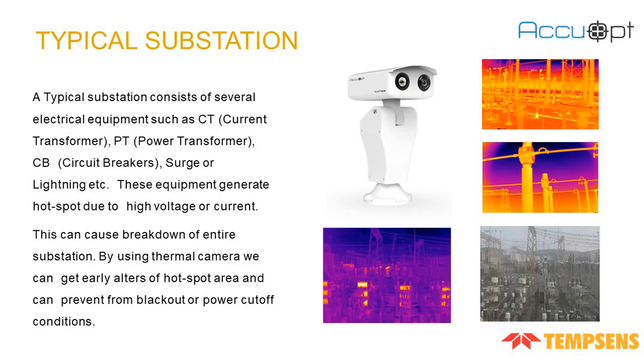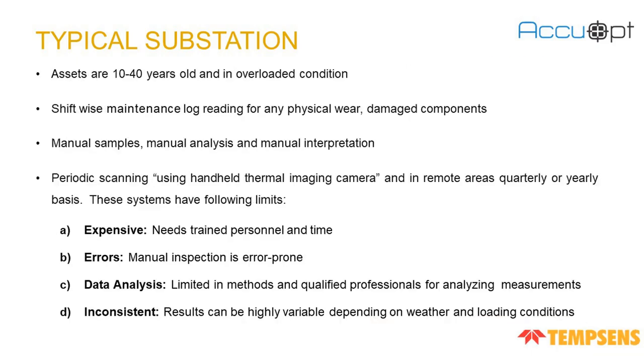Moving towards today's topic, the substation hotspot monitoring system. In a typical substation, there are various electrical equipment such as current transformers, power transformers, circuit breakers, surge or lightning arresters, etc. This equipment generates hotspots due to high voltage and current. Due to this, the breakdown of the entire substation can happen. By using a thermal camera, we can get early alerts of hotspots, and it can prevent blackout or power cutoff conditions.